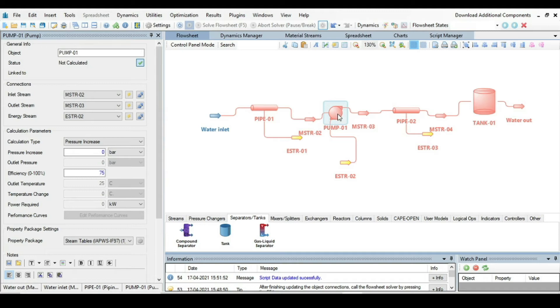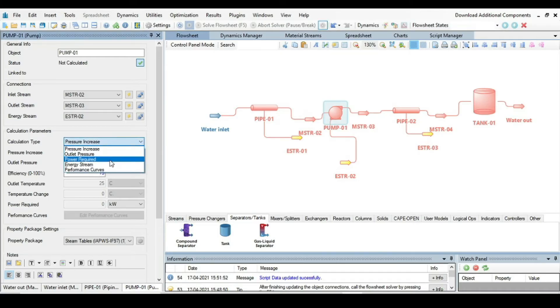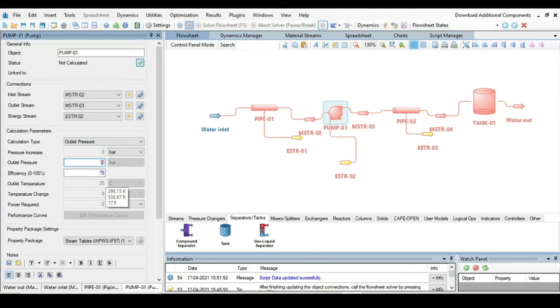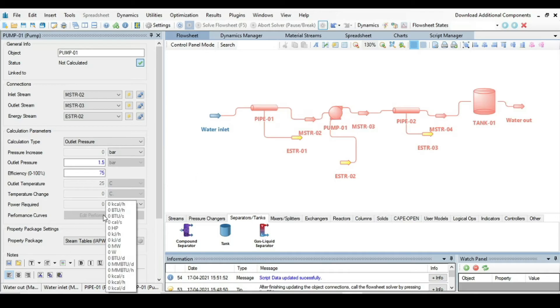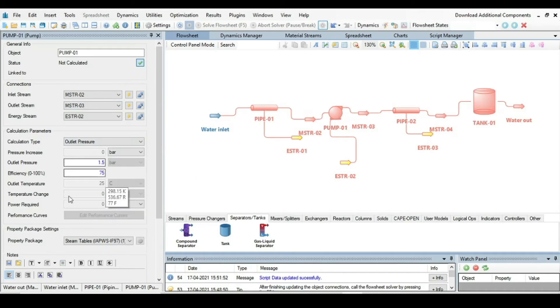Next, specify the pump. Set the efficiency to 75% and specify an initial outlet pressure of 1.5 bar as a guess, to see whether the pump will be able to cope with the pressure drop through the system from inlet to outlet. There is nothing more to specify in the pump tab at this stage.